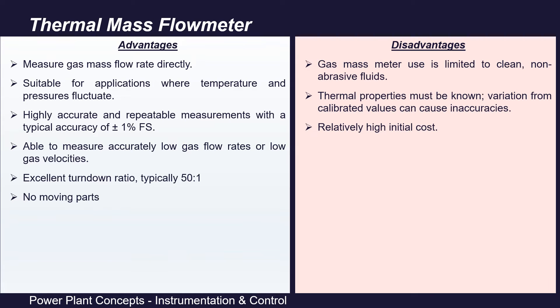And last but not the least, it has no moving parts, no wear and tear, so less maintenance. But it has certain disadvantages too. First is it can be used only for clean and non-abrasive fluids. Second is thermal properties must be known. Variation from calibrated values can cause inaccuracies.